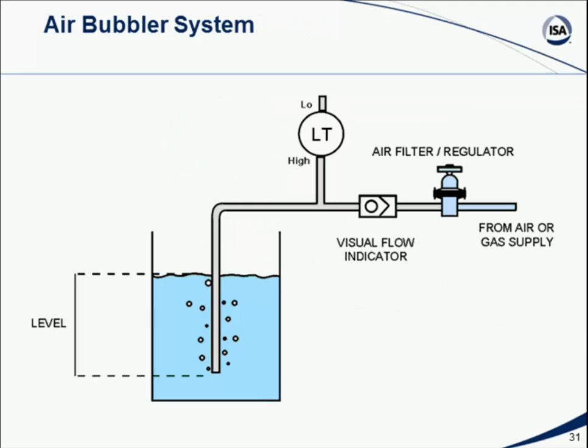Now, another way of measuring what's in a tank is, again, working off the basis that we know that the deeper the fluid is, or the higher the level of fluid is, the greater the pressure. So if I stick a pipe down into a fluid and blow into that pipe, no air will come out the bottom of that pipe until I'm blowing into the pipe hard enough such that my air pressure into the pipe exceeds the fluid pressure that's trying to push back up into the pipe.